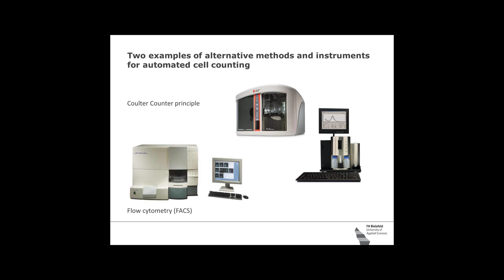And the Coulter counter basically measures the electrical resistance over a pore, and the resistance, if there is only liquid in this pore, is constant. If a particle enters this pore, the liquid gets replaced by the particle, so the resistance over the pore is different, it gets higher. From this information, you can calculate cell diameter. To do so, the cells or particles that enter the pore should be ideal round objects. If not, you get the wrong information. So that's one assumption you make that may lead to results that may not be that precise.